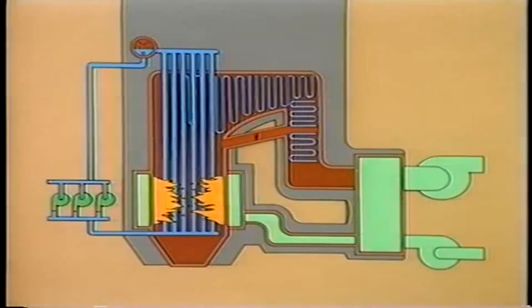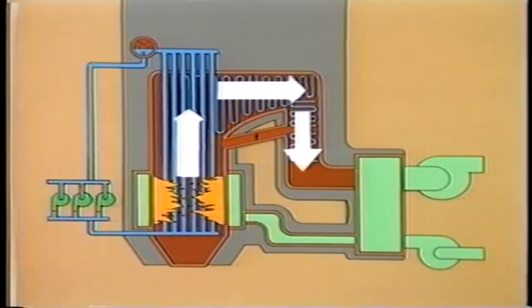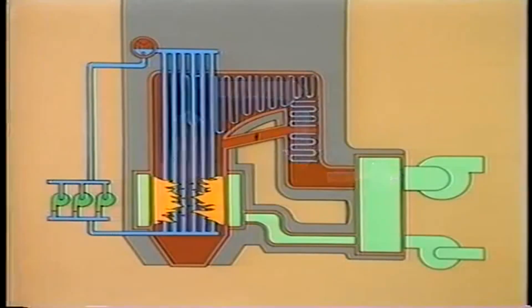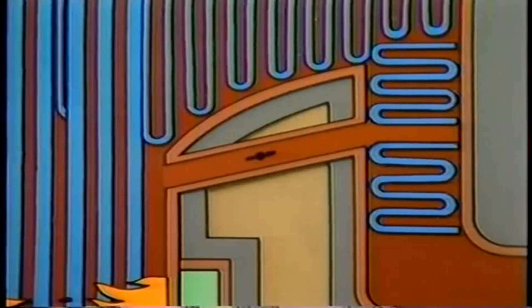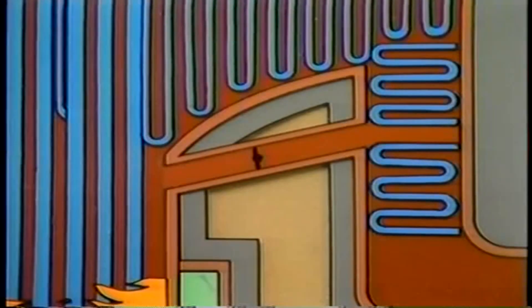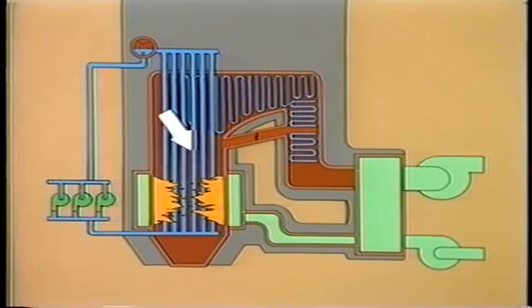Another situation that can lead to a boiler explosion is difficult to detect and may cause an explosion with no warning whatsoever. To give you one example, we'll use a boiler that has a gas bypass system for steam temperature control. Under normal conditions, flue gas flows from the furnace area over the superheaters and reheater, over the economizer, and then through the air preheaters. In a boiler with a flue gas bypass, if the outlet temperature of the superheated steam gets too high, a damper is opened which redirects a portion of the flue gas away from the superheaters. When superheated temperature returns to normal, the damper is closed and flue gas flow proceeds normally. Gas bypass systems usually do not require the use of fans — flue gas can be redirected simply by opening a damper, because the pressure in the upstream section is higher than in the downstream section, and fluids naturally flow from higher to lower pressure.